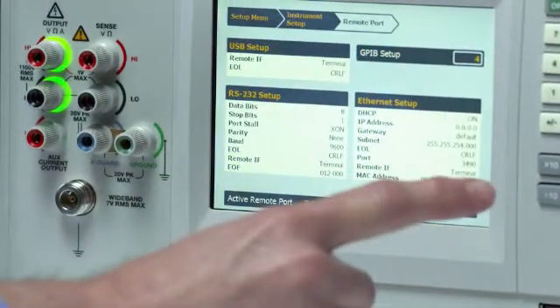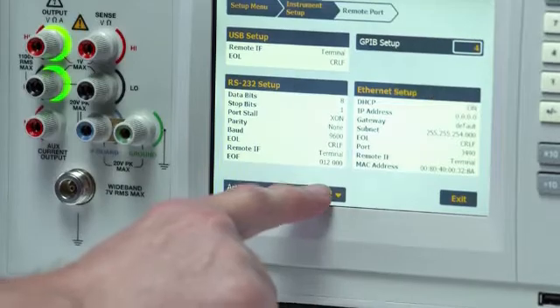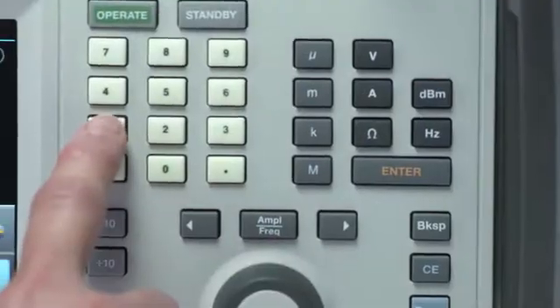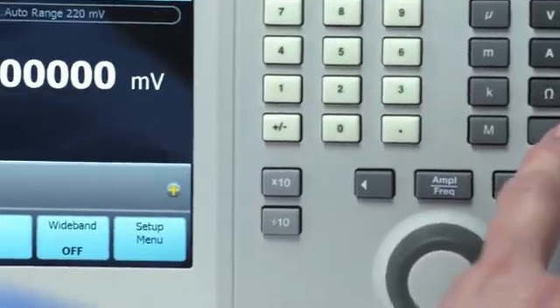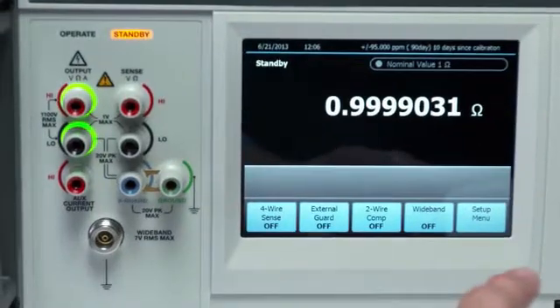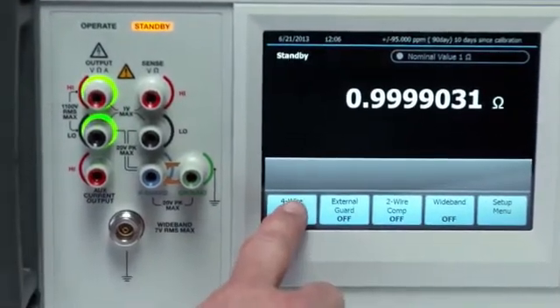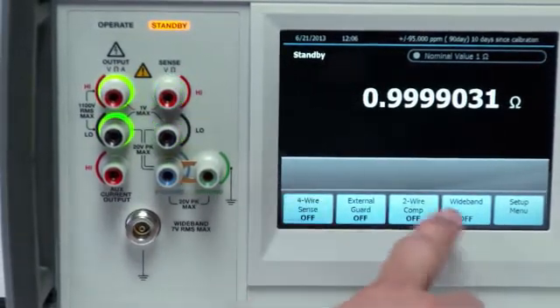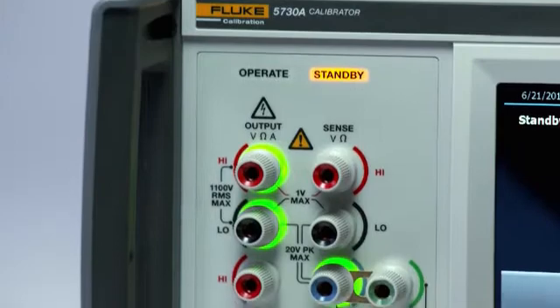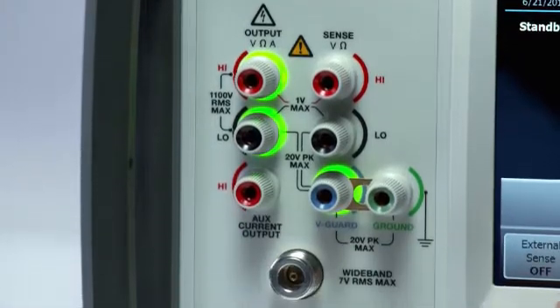Navigate and change settings quickly and easily using the streamlined setup menu. The 5730A visual connection management terminals help users make the correct cable connections based on the specified output. Enter a value and the appropriate output terminals light up to indicate those that will be live. This feature eliminates simple connection errors and helps prevent instrument damage.